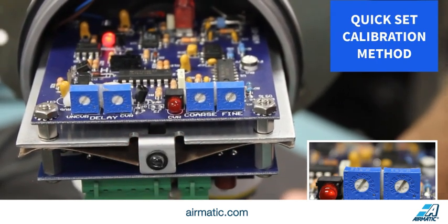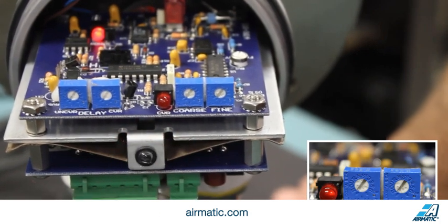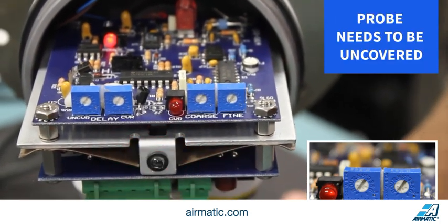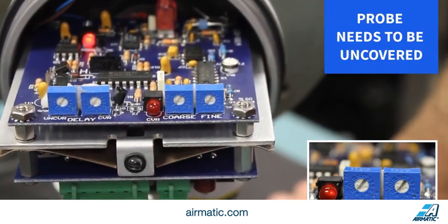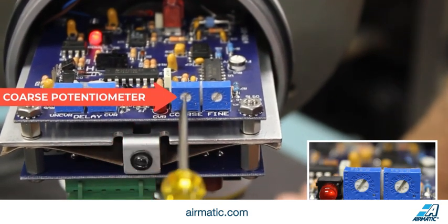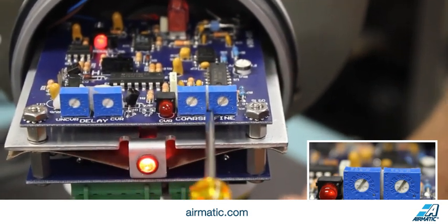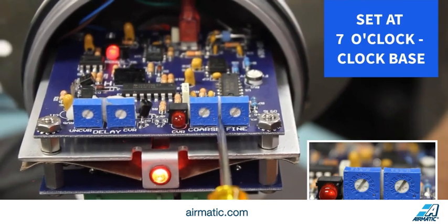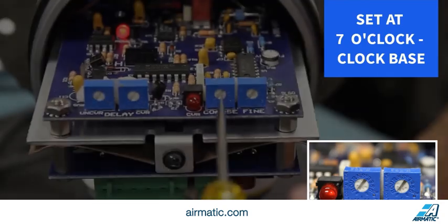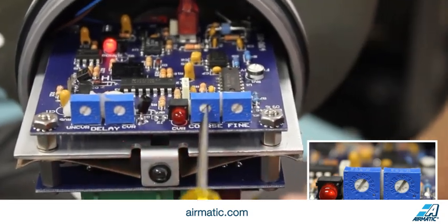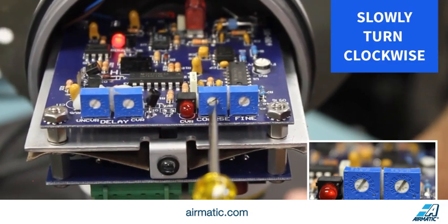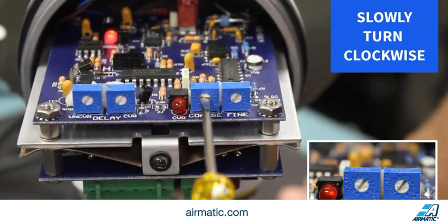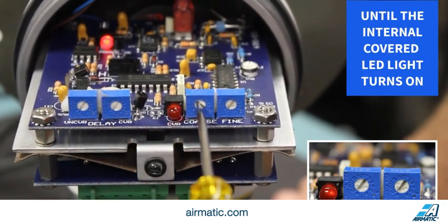We're going to start, we need to have the probe, the capacitance probe, uncovered so that there's no material in contact with it. And we'll start with the coarse potentiometer. We turn both potentiometers to their full counterclockwise position. So first we'll go to the coarse potentiometer, and we're going to slowly turn it clockwise until the covered LED right beside it just turns on.